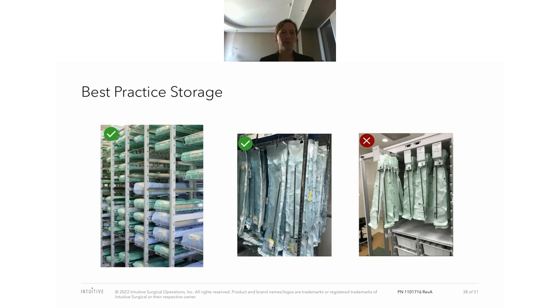And I just want to highlight one thing in regards to peel pouches, since we're also talking about peel pouches in this webinar. You can see the middle picture where the peel pouches are hanging and the housing is towards the bottom. And on the right-hand side, the housing is actually on the top and the tips on the bottom. So this is something to be a bit careful about, because the pressure and the weight of the whole instrument lies on the tip, and it could then pierce through the sterile wrapping, through the peel pouch, which would lead to it being unsterile and has to be reprocessed. Sorry about that. And that is something that can be avoided. On top, it could also lead to damage on the tip.